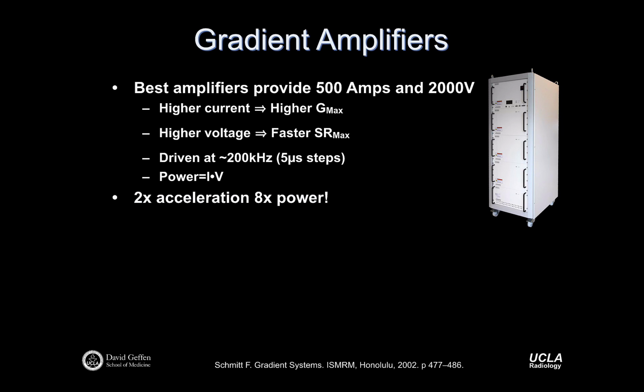They're driven at really high raster rates. Depending on the system, we can command the gradients to do things every 2 to, say, 5 microseconds. But we can only increase or decrease as long as we fall within the slew rate limits of the system itself.